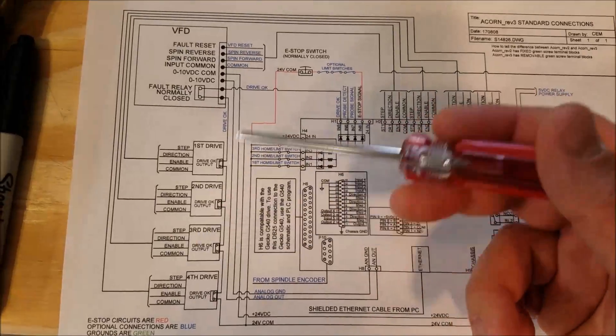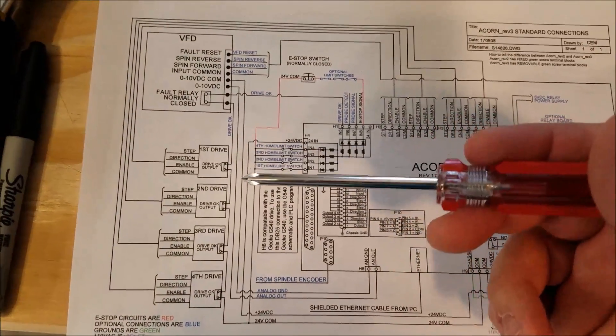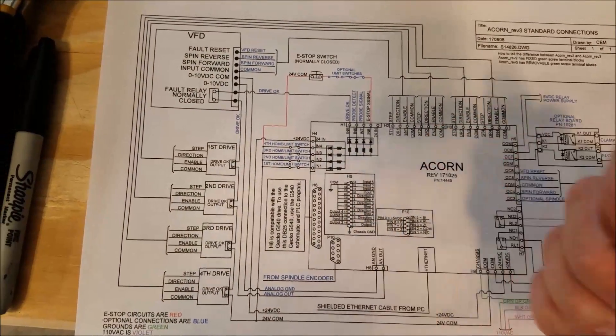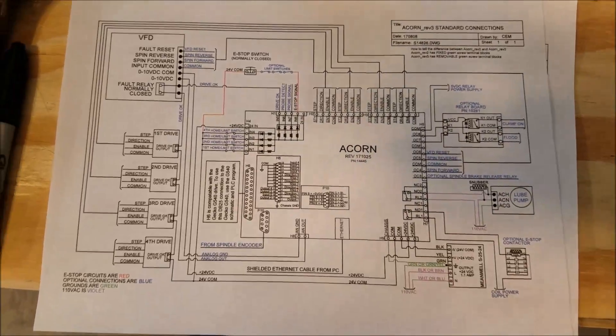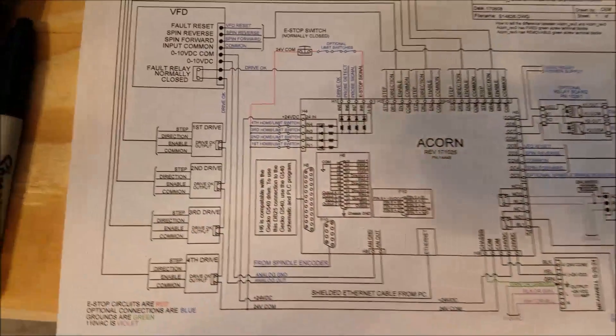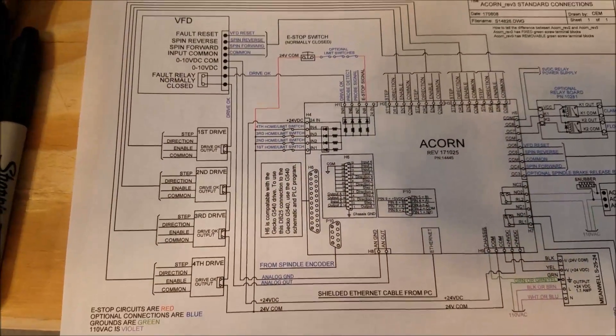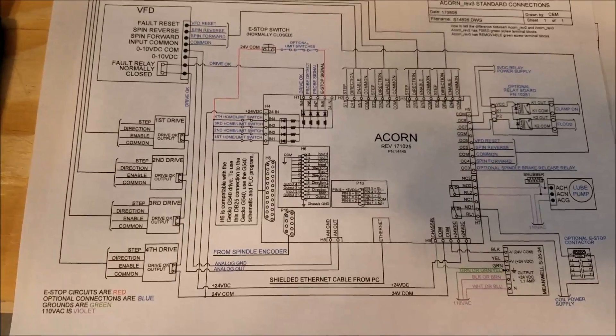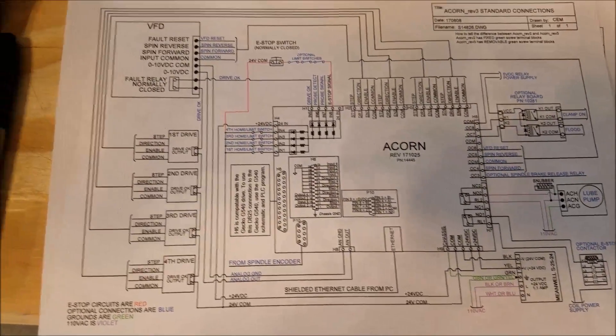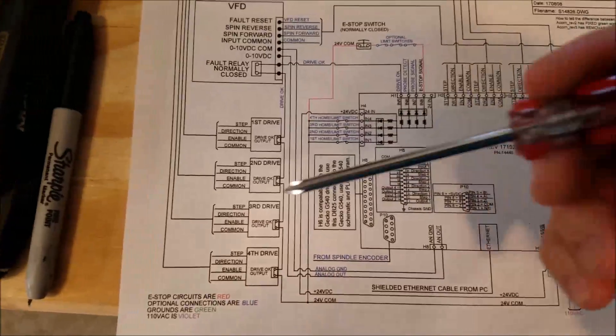If anything along the way breaks the connection—it could be any one of these drives—it triggers the alarm signal. You won't actually know what triggered it, but you'll know something happened. Then you open up your electronics cabinet and look for the drive that's flashing red or whatever, and you'll know what to fix.